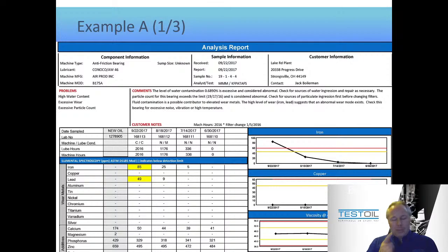But let's just say, hypothetically, that whatever's wrong with this bearing is obvious from 30 feet away. Somebody walking up to this bearing to do an inspection for how the dirt got in there can spot the problem from 30 feet away. It's just that obvious, right? The breather's damaged, the dipstick's out, the fill cap's off, whatever it was. So hypothetically speaking, it's that bad. So obviously they correct it. My question is, if they correct it, what do you do next?